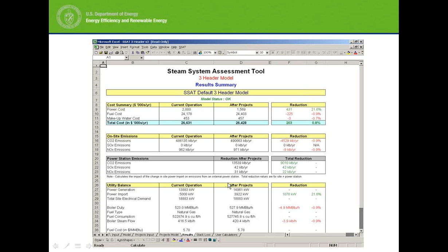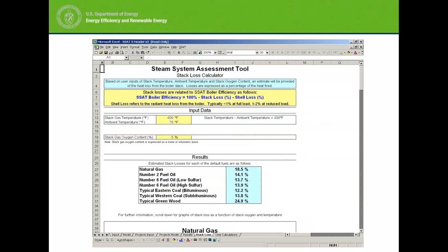As I said, the stack loss calculator can be used for boilers or even for process heating, where you have information on the stack temperature, the ambient temperature, and the oxygen content.